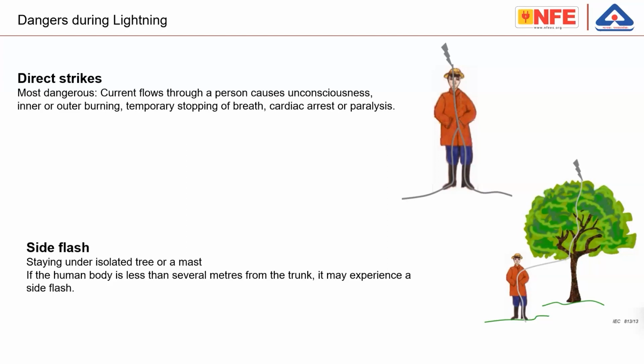For example, instead of a tree, imagine a wooden pole. There are some propagandas going on in India using a cycle tire and a wooden pole. If you have an 8 mm conductor connecting the cycle tire to the earth electrode, and if the joints are not proper, side flash will happen. And if there is any bend in this 8 mm wire, or a bend in the down conductor, side flash may happen.